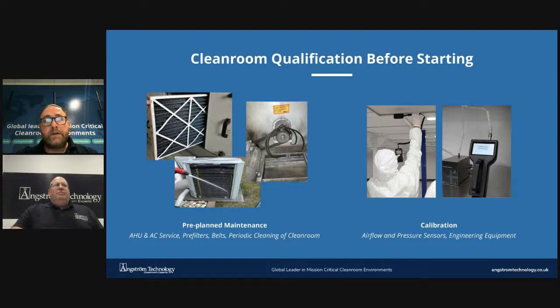Secondly, calibration of equipment. This not only covers the sensors you may have within your facility, such as airflow and pressure sensors, but more importantly, this is for the validation engineer's equipment. All the kit used by an engineer should be in good working order and calibrated because it helps ensure accurate, repeatable measurements. These are the foundation of the quality, safety, and innovation of most products and services we use and rely on every day.